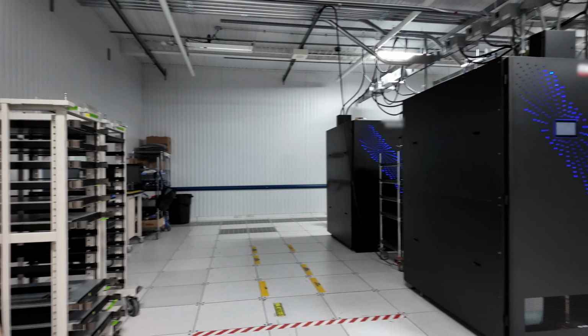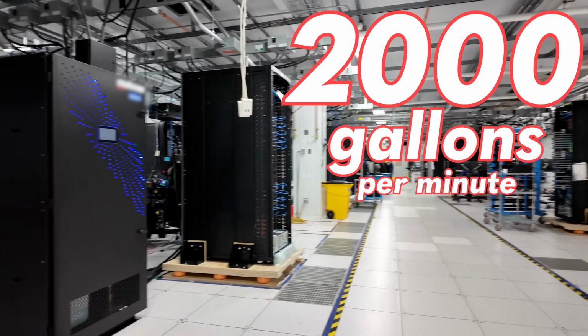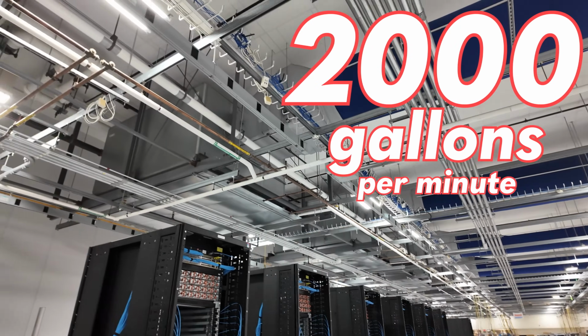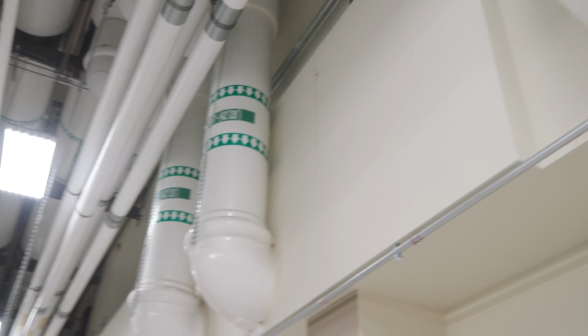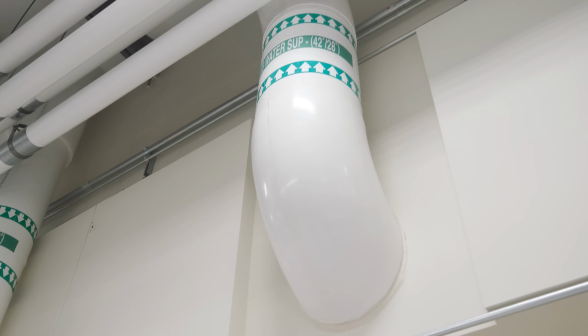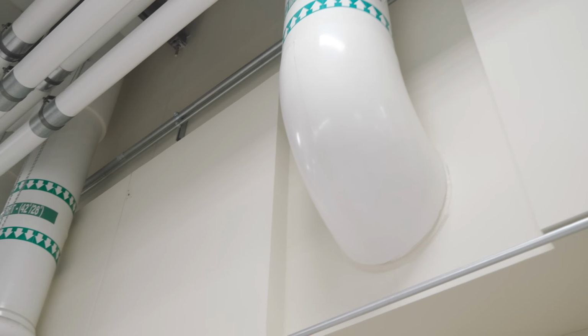Now, these, of course, are primarily liquid-cooled systems. And so overall, there's CDUs that can push something like 2,000 gallons per minute to the chiller architecture in this building, plus there's all the HVAC systems that just cool the air. And so if you come outside of the room, you're going to see just a small sample of all of the piping.